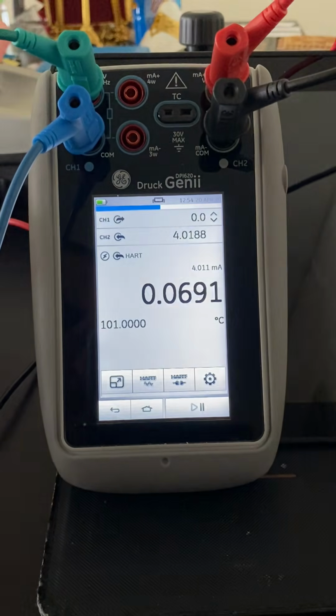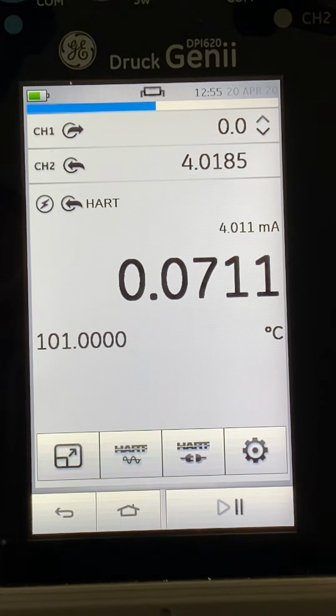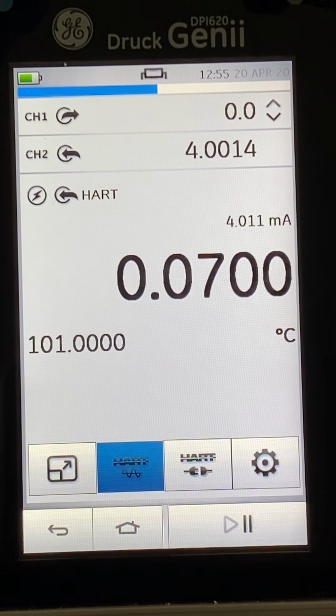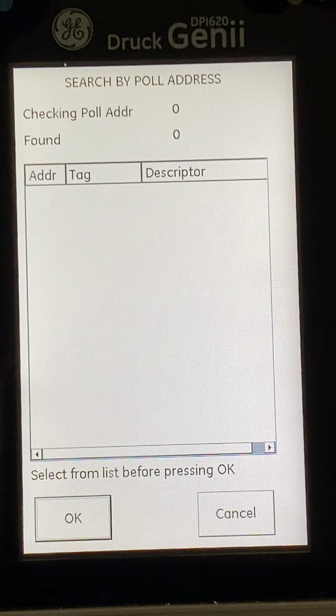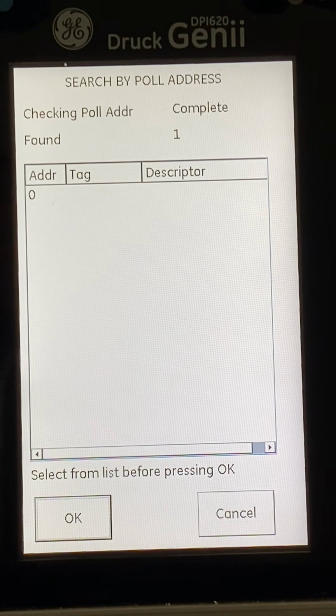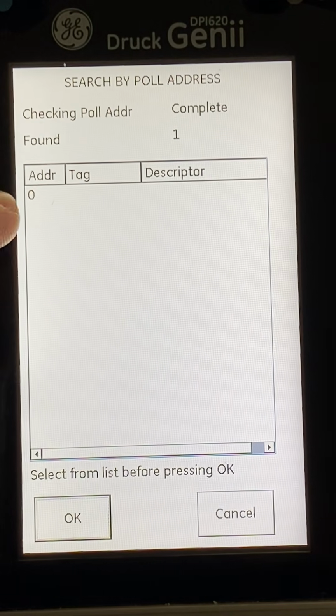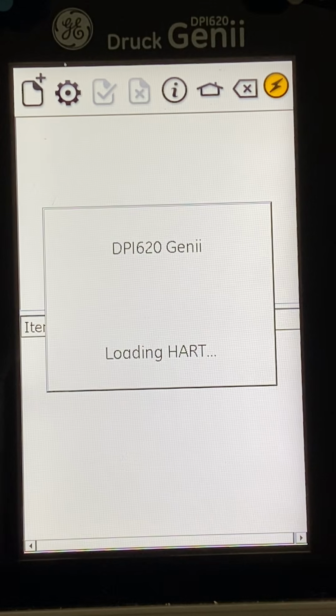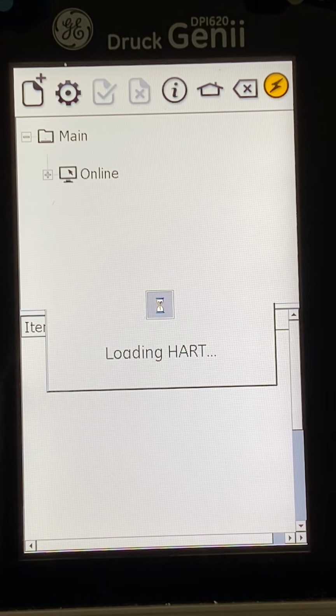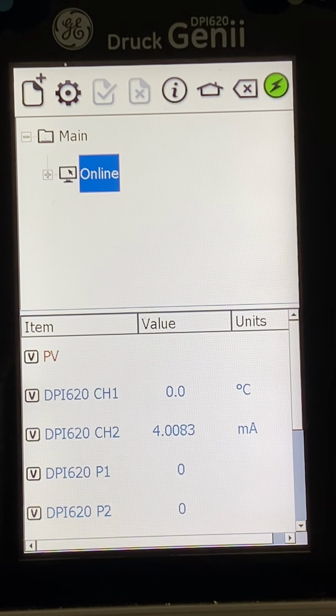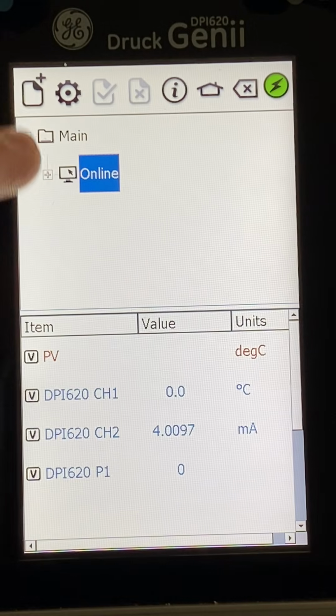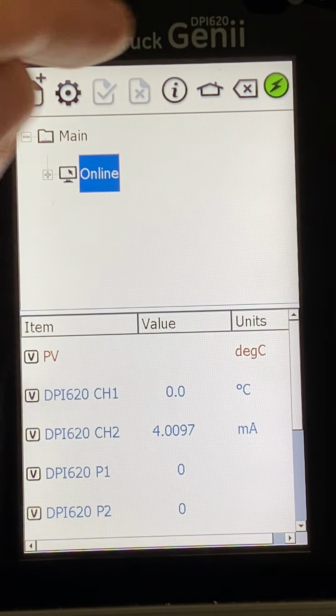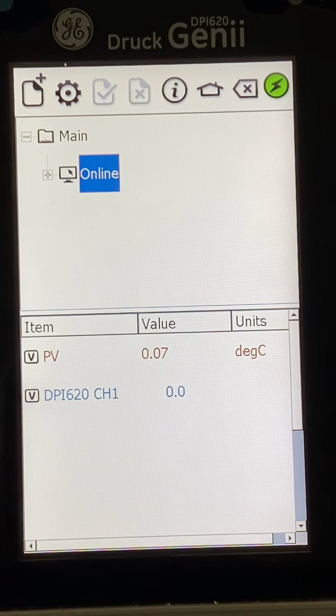So here are the connections, and I'll be just zooming in the screen to make it clear. So I'll press on the HART. Now the device or the communicator will start scanning or searching by poll address. They found my device on address 0, so I'll just press OK. This will take me to the HART menu, where I can start and do the adjustments or the programming. Okay, this is the main menu. It will appear like a tree. So this is the online. Here is the tree. Here is the taskbar, and here is the values.